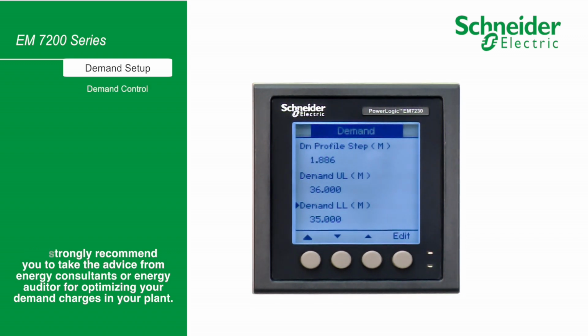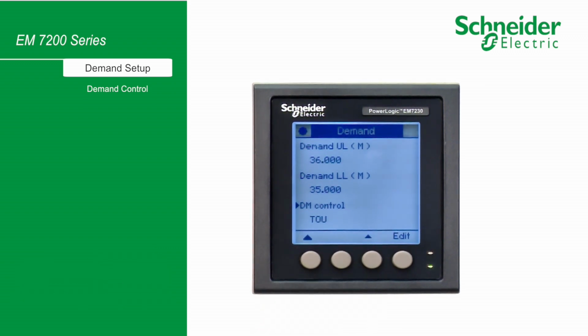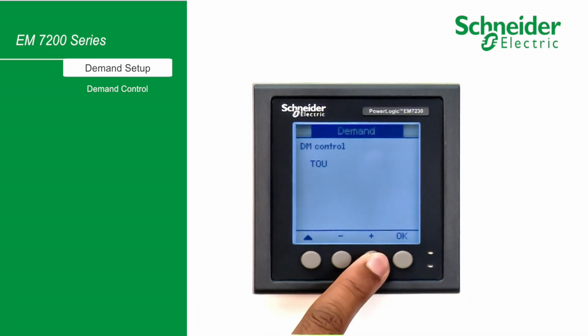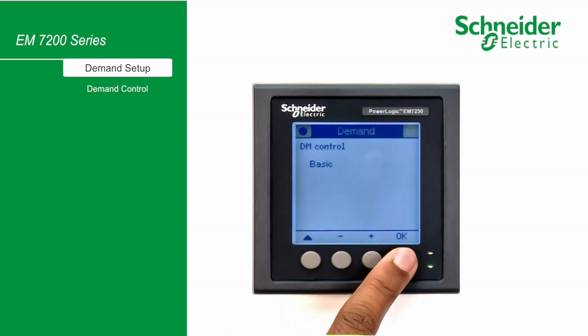From the setup page, navigate to the demand menu. Your demand controller is equipped with an advanced TOU setup feature together with basic setup. Some of the utility companies regulate their users to draw power based on the season of the year and time of the day. If you want to control the demand without considering TOU regulations, the basic option can be chosen. For TOU settings, please use ION setup, which is available free on the Schneider Electric website. Please refer to the TOU settings video. Let's select Basic. Press OK.